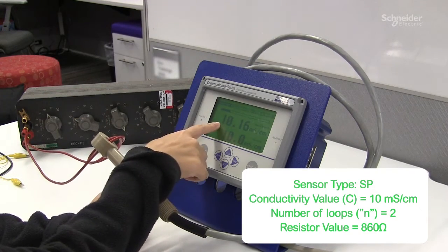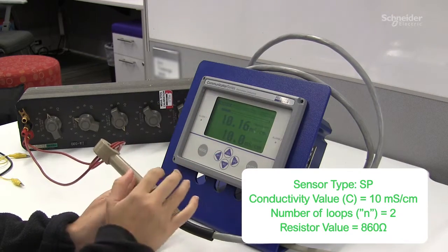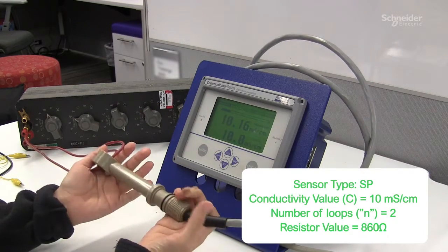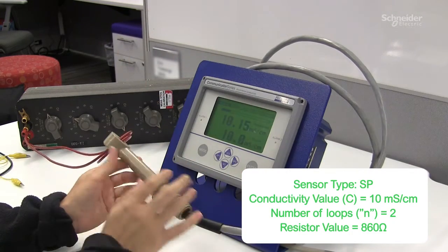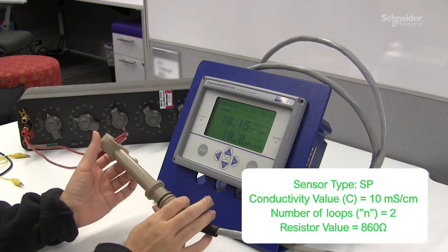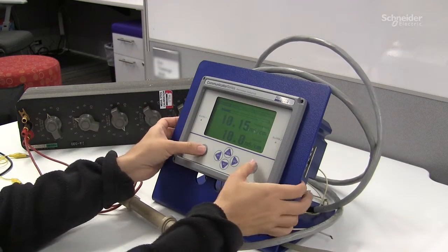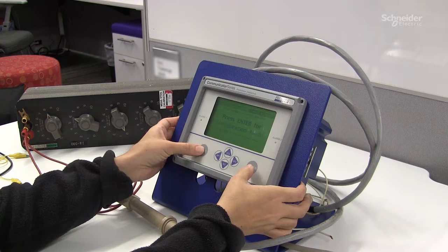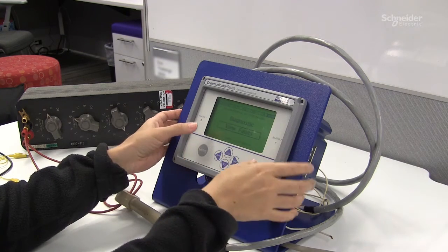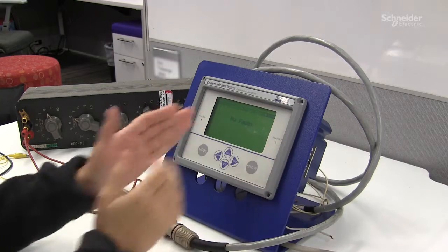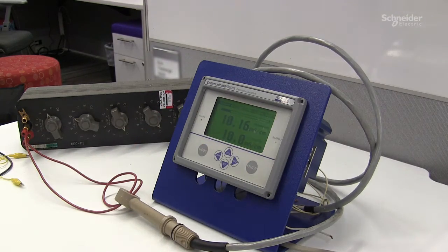There it is. So now we have confirmed that our analyzer and A71 EC sensor, that is our complete conductivity system, has been calibrated and is working correctly and we have no more faults displayed. You can still confirm that going back to the diagnostic menu, view faults, and it is working perfectly. Thank you for watching.